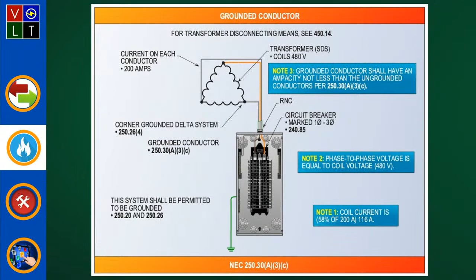And that's what they're going to talk about here, where you're dealing with a separately derived system and it's delta. So is that technically a single phase then? Yes, that's single phase. Matter of fact, if you look, you'll see there's only the brown and orange coming in. Okay. And we show that because we're showing you the coils there for that 480 volt transformer. It's hard to see in the illustration how the ungrounded conductors tap to that breaker. The other one is sort of hard to see, but that's a gray conductor for the neutral. And that could be white too, right? It could be. It depends on how you set it up.